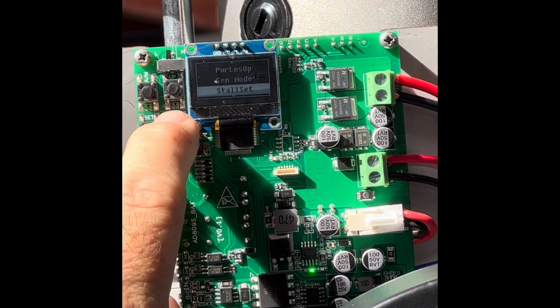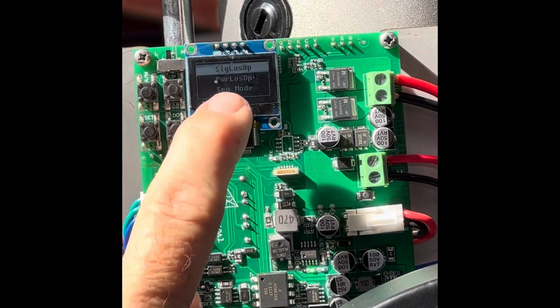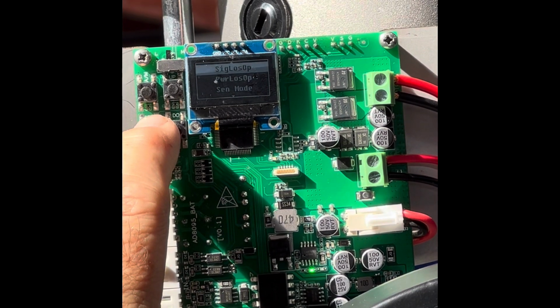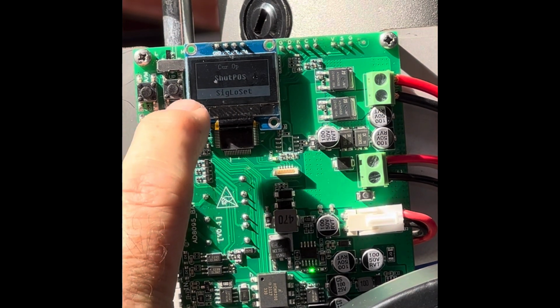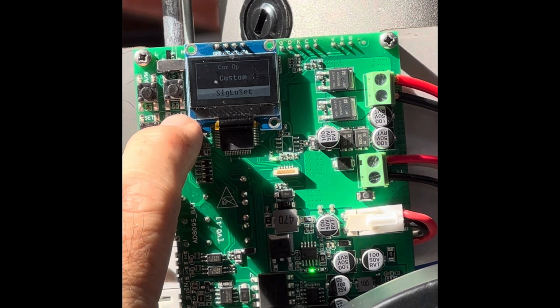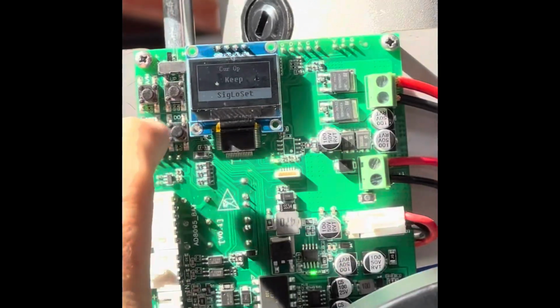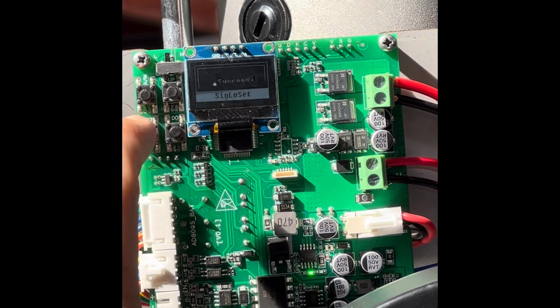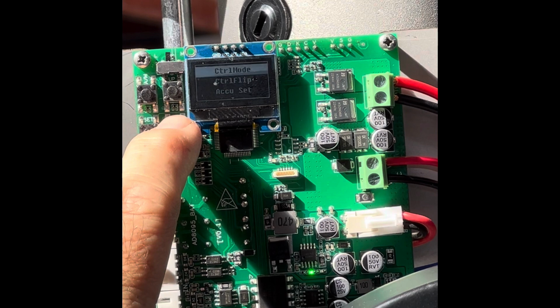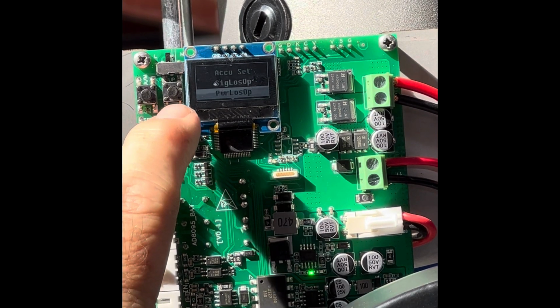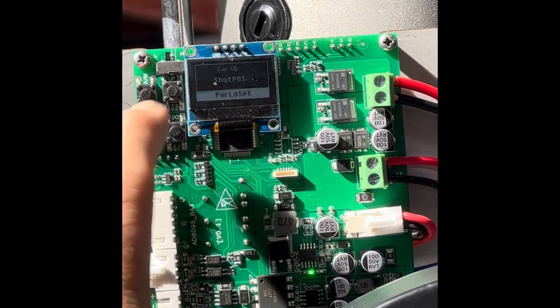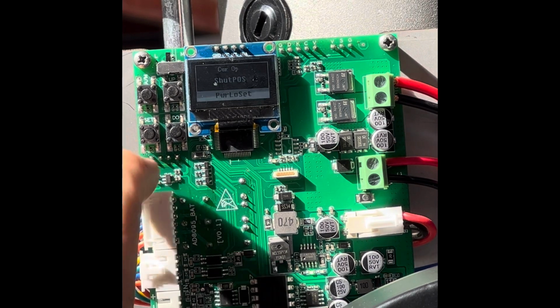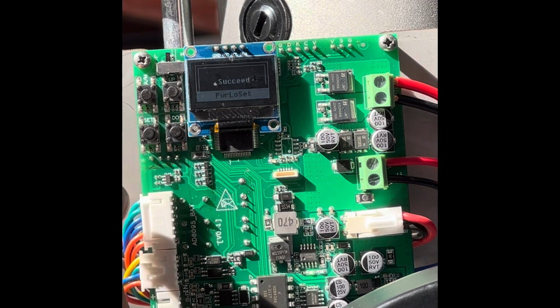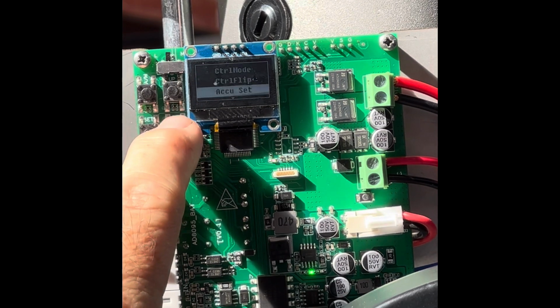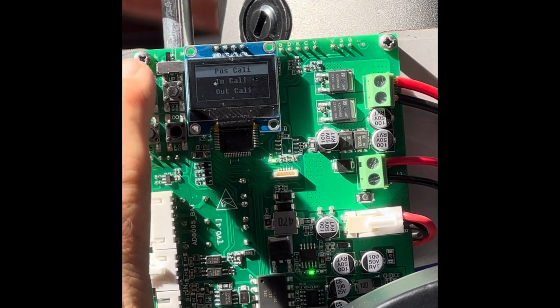Go down till you get, let's see here. Okay, signal loss. I want this to fail close on loss of 4 to 20 signal. But I can also make it fail at any percentage between 0 and 90. I can fail it in place. I can fail it open, but we're gonna make it fail close, which is called shut position. Set that, go back. Now power loss. If you got a battery backup, you can set this to fail open, close, in place, or a percentage of travel. So I'm gonna set this to fail close, set, go back. Okay, then just back out of this.